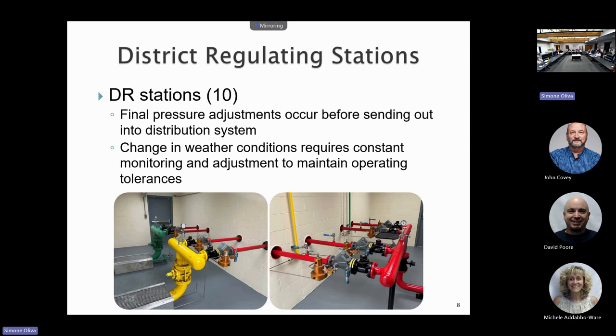You can imagine some of the days we had in the last month and a half, where we saw 55 degrees during the day, and then a front comes in and it's 10 degrees at night. If we have our regulators set to handle 55-degree load, almost nobody's using their heat. Then all of a sudden everybody's heat turns on, their Nest thermostat or whatever decides it's getting cold outside, they all turn on at once, and the pressure can drop very quickly in the system.